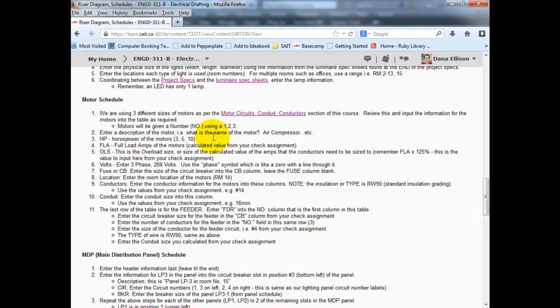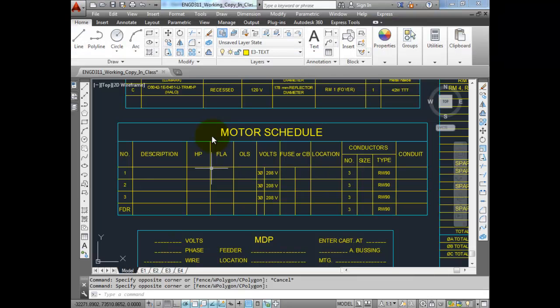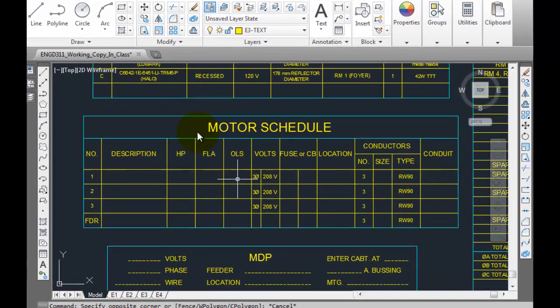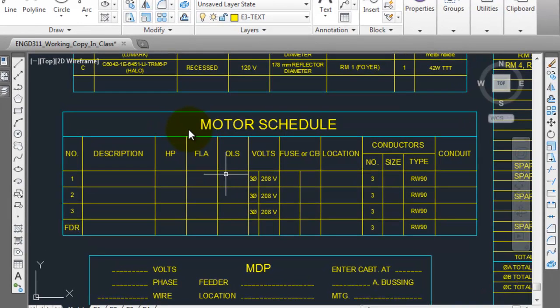So remember that step where we did the full load amps multiplied by 125% and we came out with an amperage that we were then going to look for in the ampacity of the conductor. That's the value that you want to place in here.